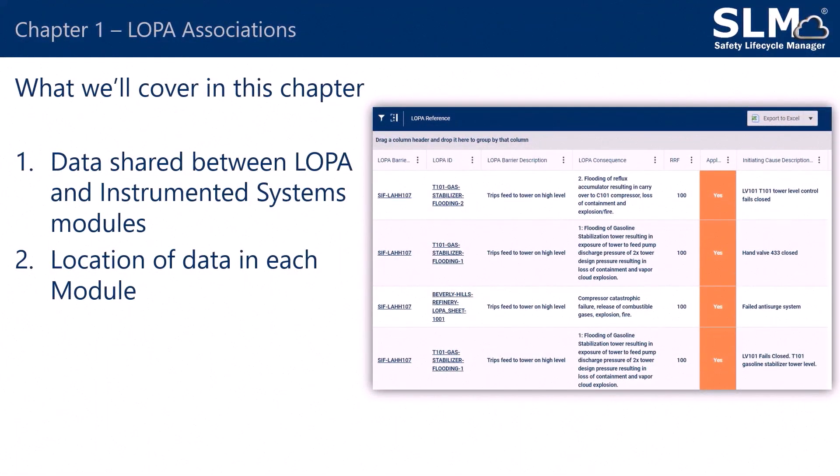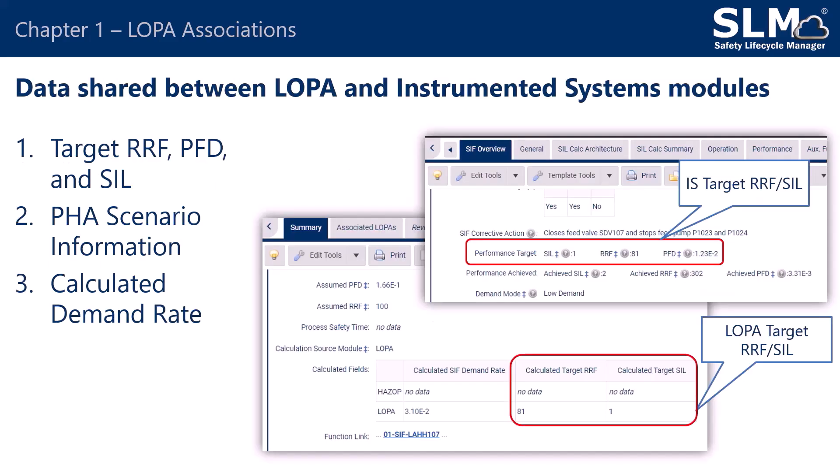In Chapter 1, we'll be covering data shared between LOPA and Instrumented Systems modules, and the location of data in each module. There are three main grouping categories of data shared between the LOPA and the Instrumented Systems module. First is the target risk reduction factor, which is also associated with the target probability of failure on demand and the safety integrity level for those IPLs. Second is the PHA scenario information, and third is the calculated demand rate.